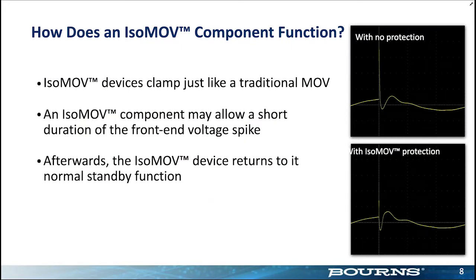So how does this thing work? What I show in the upper right-hand corner is an AC waveform, and we've superimposed a surge on top. That's a 2 kV surge on top of a 60-cycle waveform. And it clamps just like a normal MOV. You can see that on the bottom, that 2 kV is dropped down to roughly 700 volts or so. Now, because the IsoMOV has a GDT in it, you will get a little increased spark over voltage, a little spike at the front end before it enters this clamp mode. And I'll show you some details in a minute. But after the surge goes away, the MOV returns to an open circuit like normal, and it just goes on.